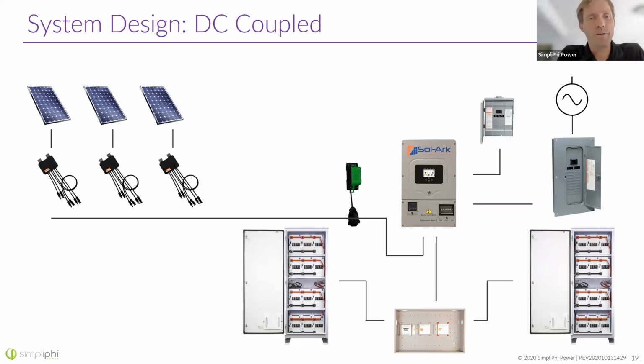Those are Tigos, right, Daniel? Yeah, those are Tigos. They look like the TS4-F. I don't believe those have the optimization in them. Okay. So some of the rapid shutdown devices have optimization, which can bypass certain panels under shading conditions. Typically for the rapid shutdown devices, you're looking at about $30. If you're getting the optimization, it can go all the way up to $100 per device.